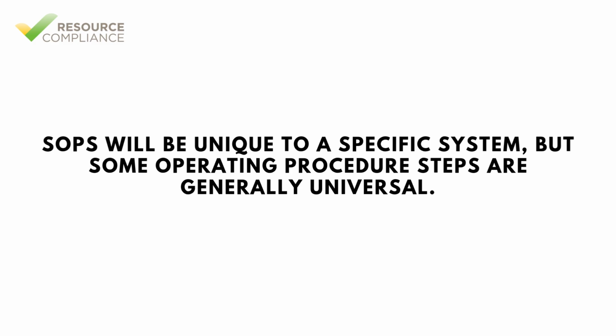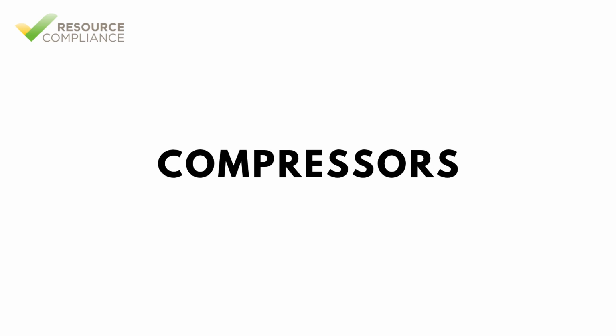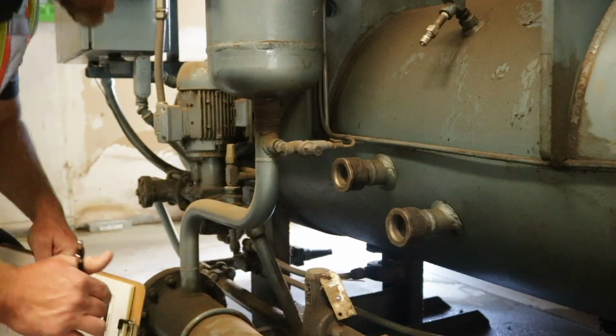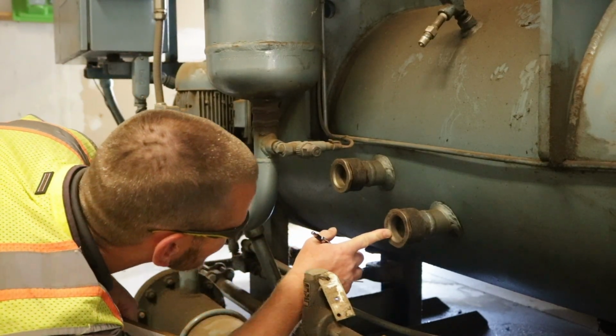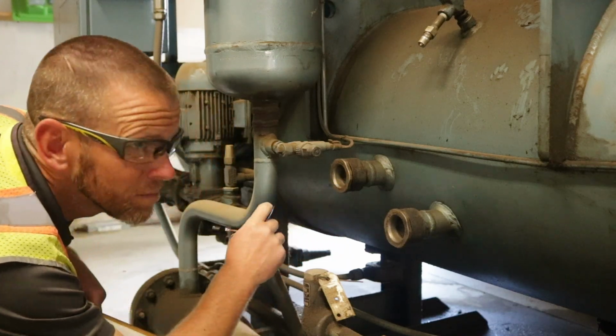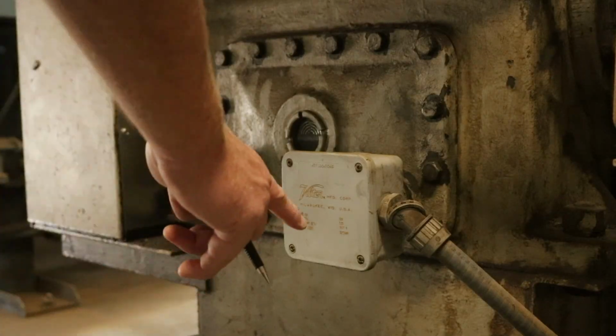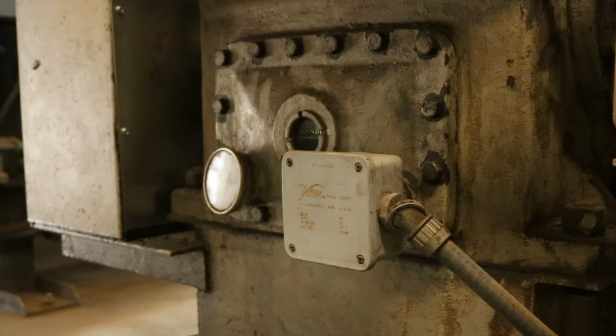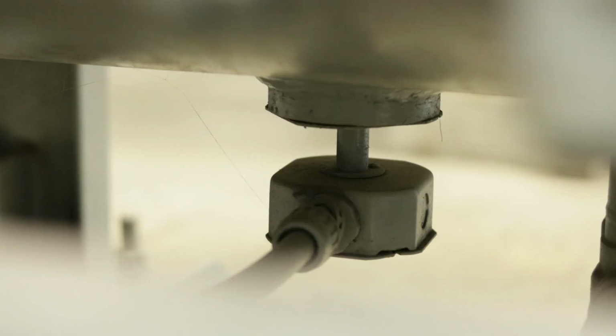SOPs will be unique to a specific system, but some operating procedure steps are generally universal. When starting a compressor, the operator must make sure that the lubrication system is ready. This means that the oil must be at the proper level and temperature. Reciprocating compressors are configured with a crankcase oil heater, and screw compressors have oil heaters in the oil separator. These are designed to be on when the compressor is off or in standby mode.